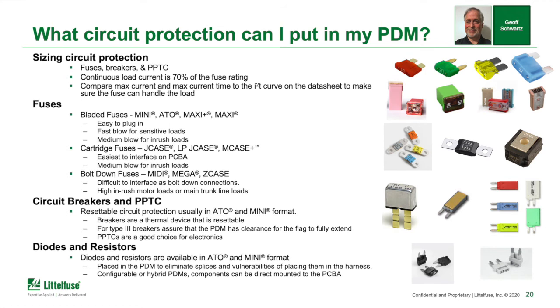What circuit protection can I put in my PDM? Again, remember the rule of circuit protection sizing. For fuses, breakers, and PPTCs, the continuous current should be 70% of the fuse rating. And what that means is, for instance, if you have a 100 amp load, you should take a 150 amp fuse for that 100 amp load. And that's simple math. You divide the 100 amps by 0.7, it comes up to about 143 amps. The next available size is 150 amps. So a 100 amp load, continuous load, should have a 150 amp fuse.